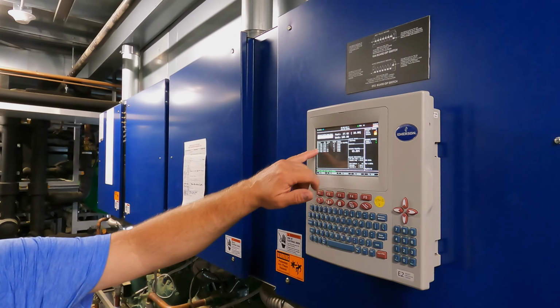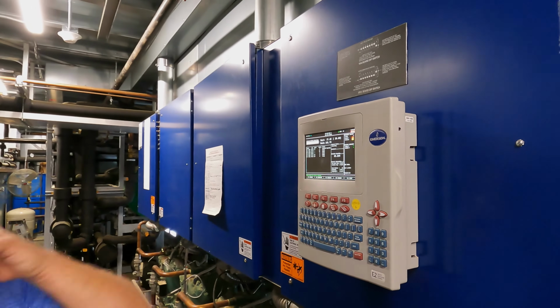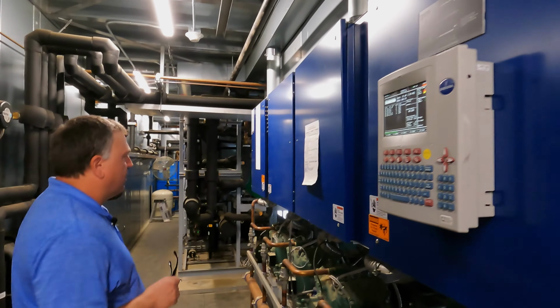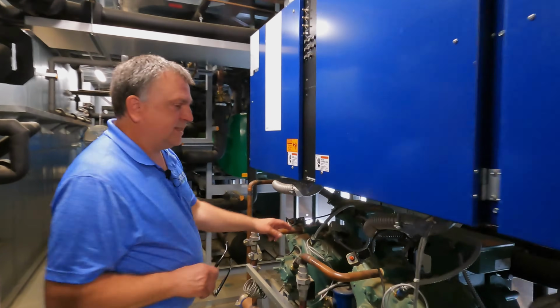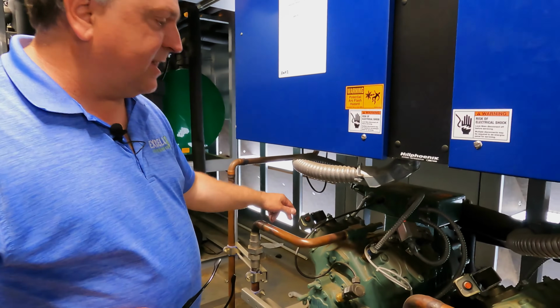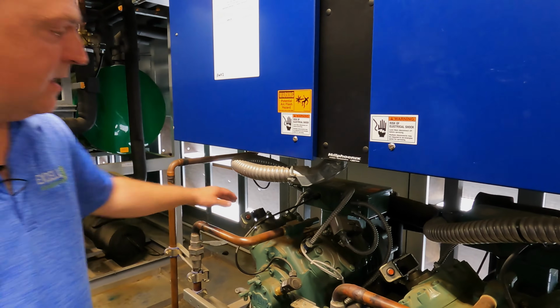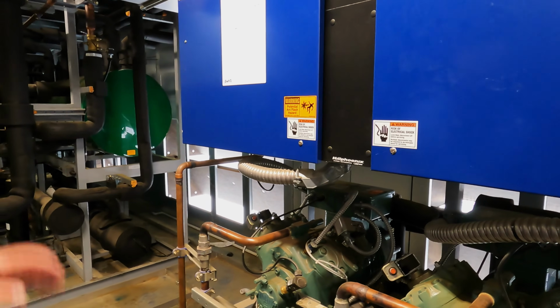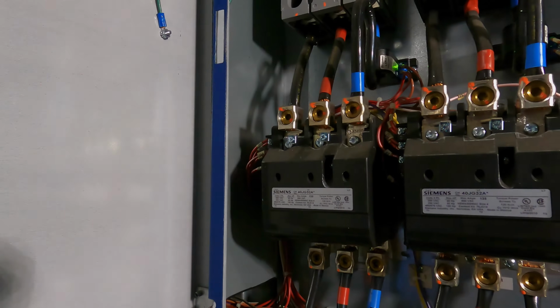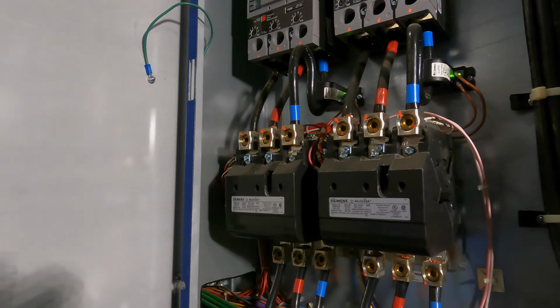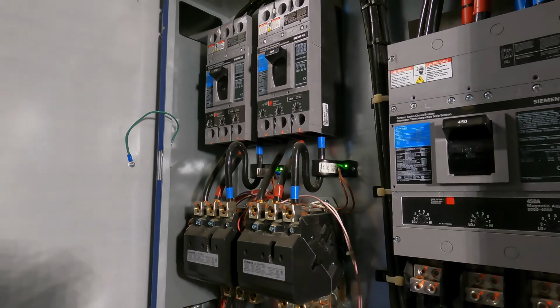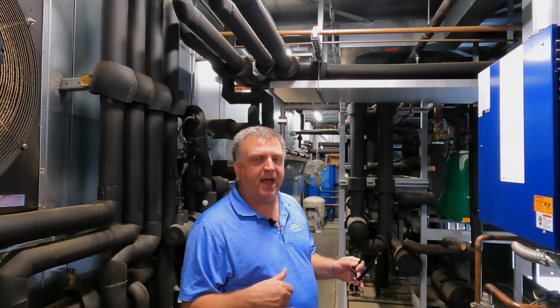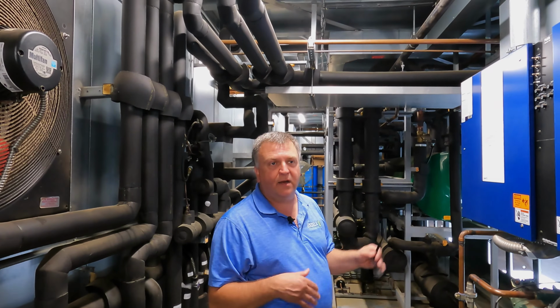With the digital unloader, this compressor will remain on all the time. All we're doing is energizing this, or energizing this, or both at the same time. If both of those are energized at the same time, that compressor is doing no work. But the contactor stays energized, the pistons stay running, and I don't have that high load amp every time I turn a compressor back on.